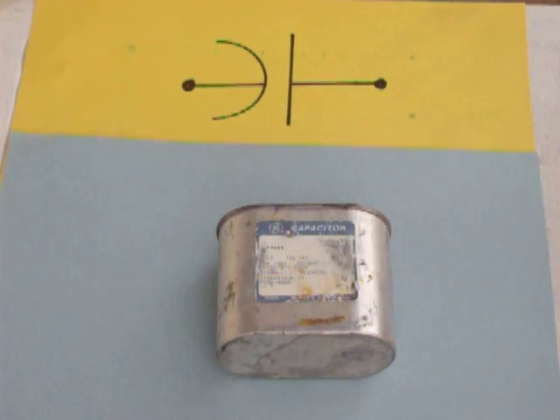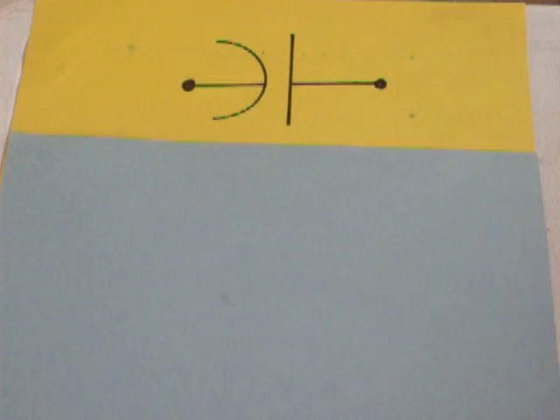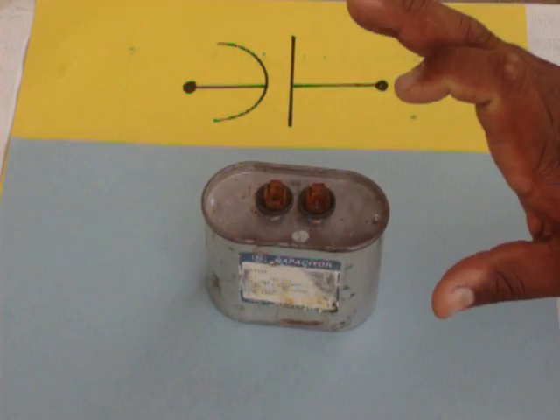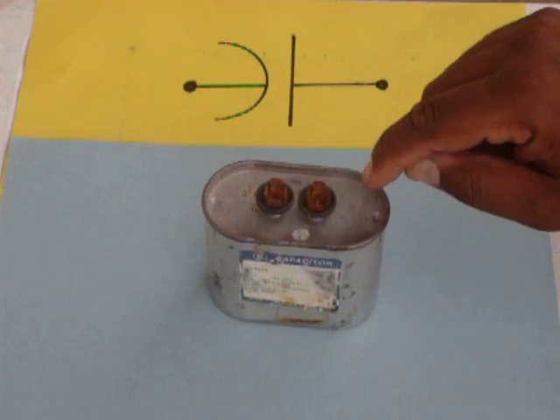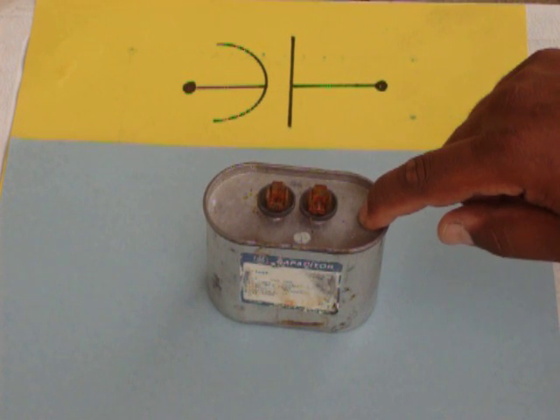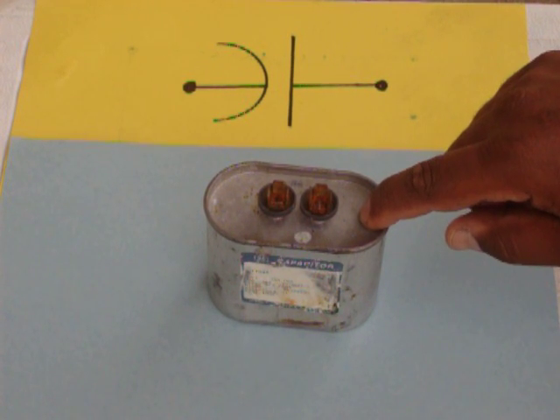This is an actual run capacitor out of an air conditioner. The concern first and foremost here is safety. Before you check a capacitor, you need to discharge it. A capacitor holds the charge. It needs to be properly discharged with a 20,000 ohm resistor.